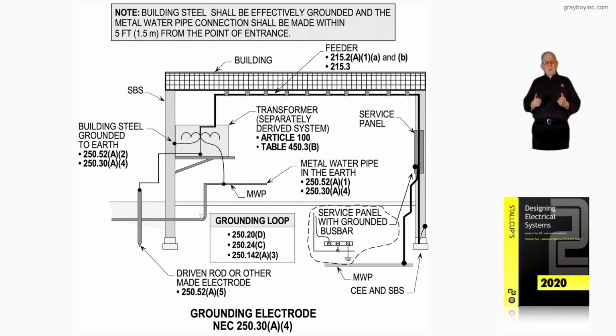And the conductors are sized at 125%, as the overcurrent device is sized at 125% for that primary under the conditions of Table 450.3(B), as in boy, of the NEC. Now the secondary side, I still think the first choice would be the structural steel to ground the secondary side of your transformer. It could be a metal water pipe.